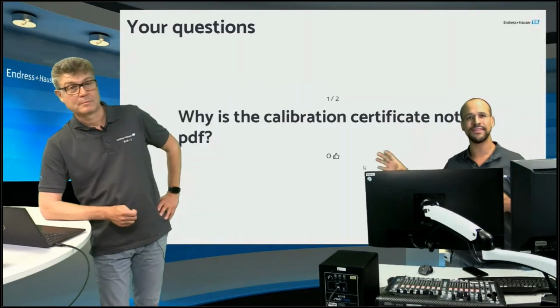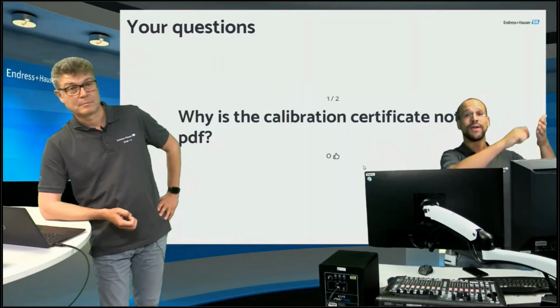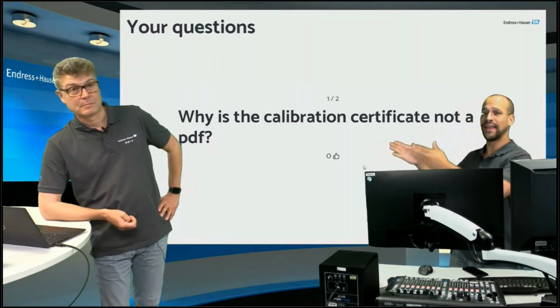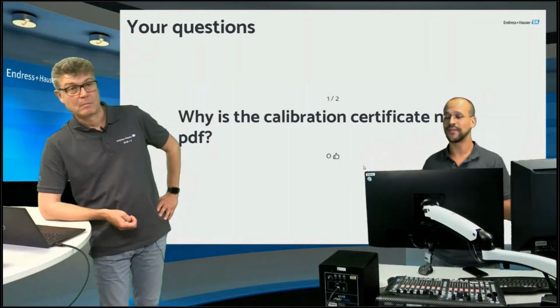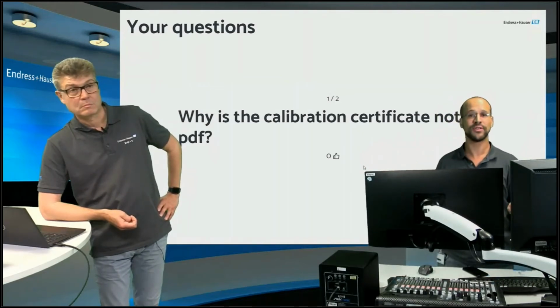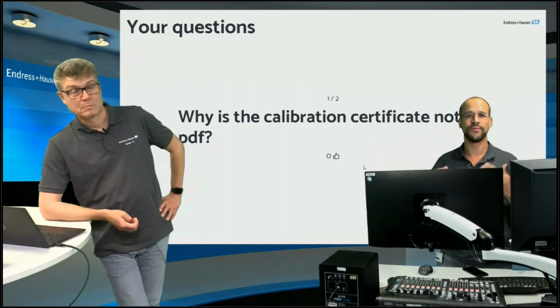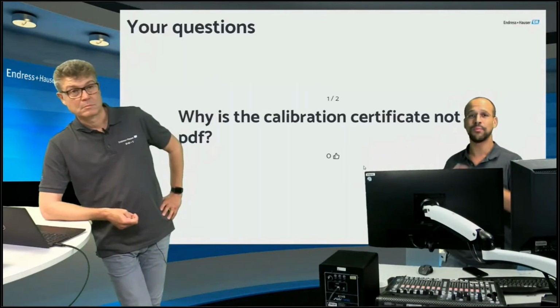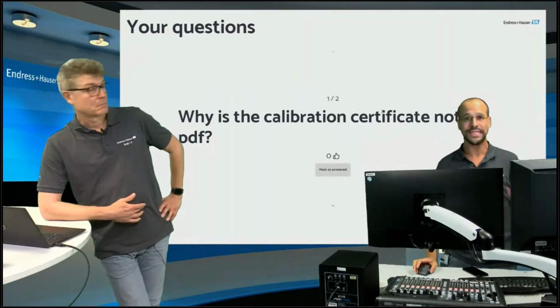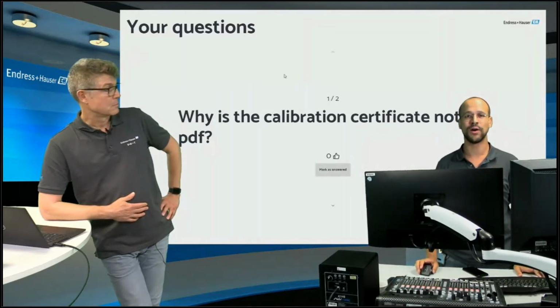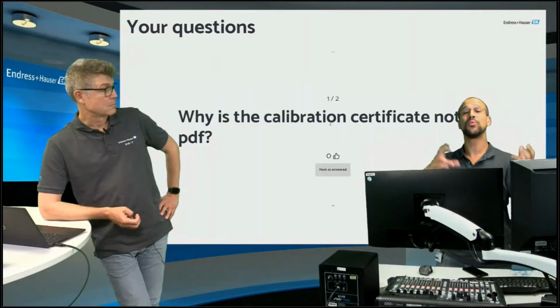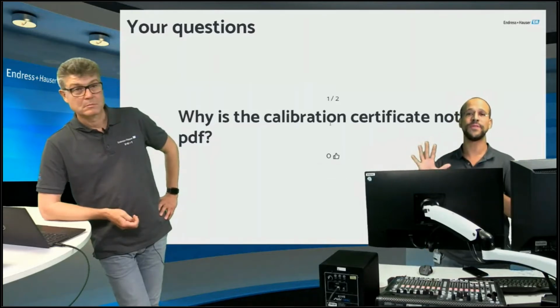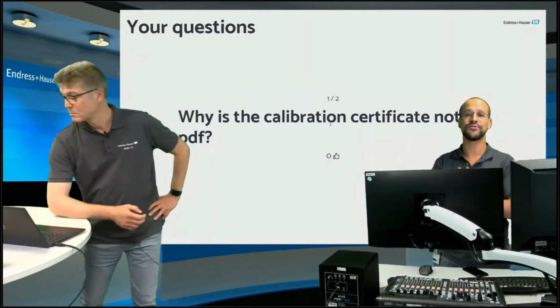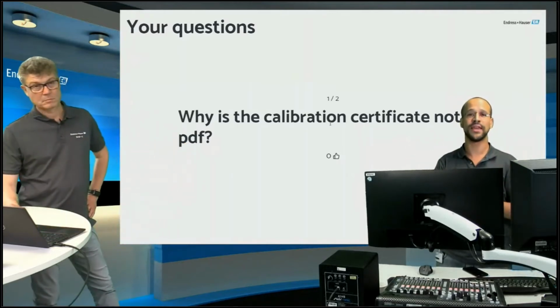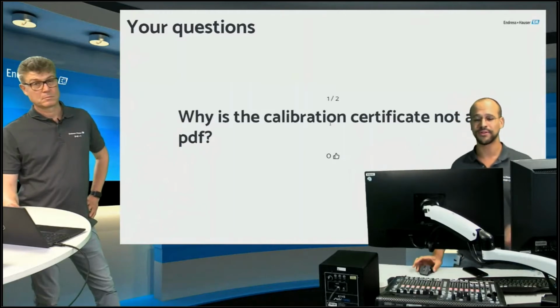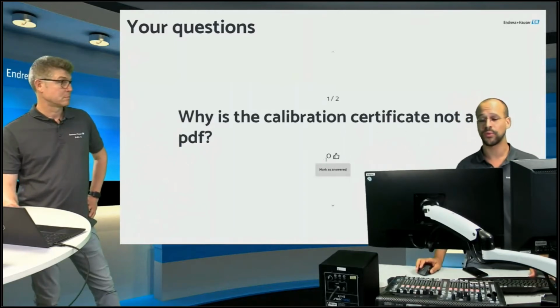And it would be the completely same thing if you do a manual calibration and you have a checklist by hand. You need to put that into a cupboard which can be closed, because otherwise someone might come and might change it, might make a copy and so on. You know how to falsify any document. So therefore, all the same with those documents. As soon as it is done, it is printed out. It should be kept safe with you. But within the Trustsense, we keep the last 350 calibration certificates, tamper-proof within the electronics. And there is another option, like Dietmar said, where we also have a tamper-proof storage together with a PDF export.